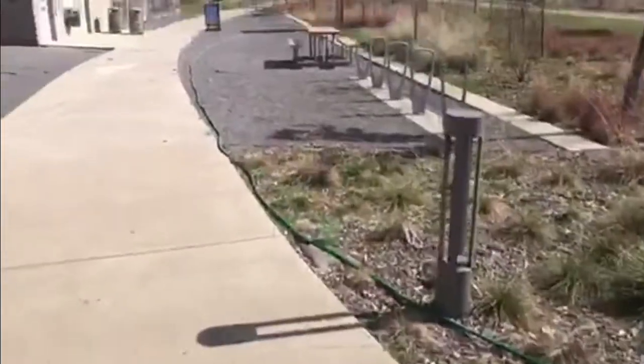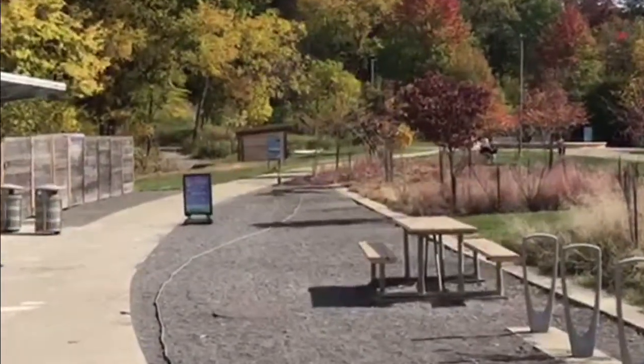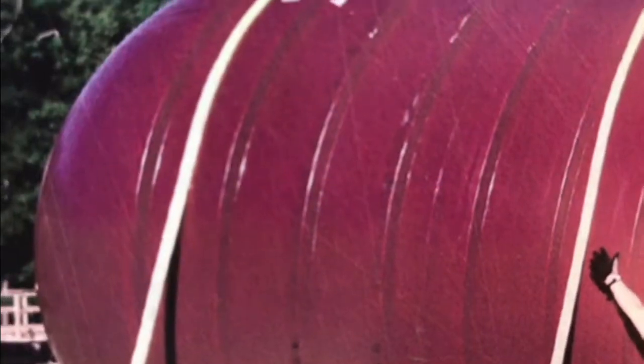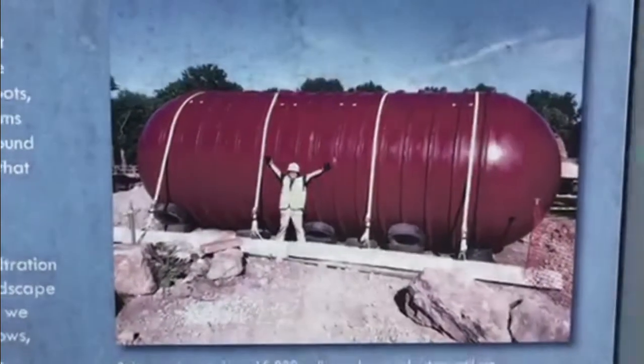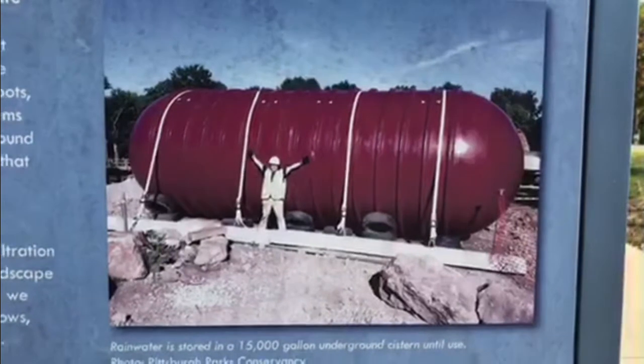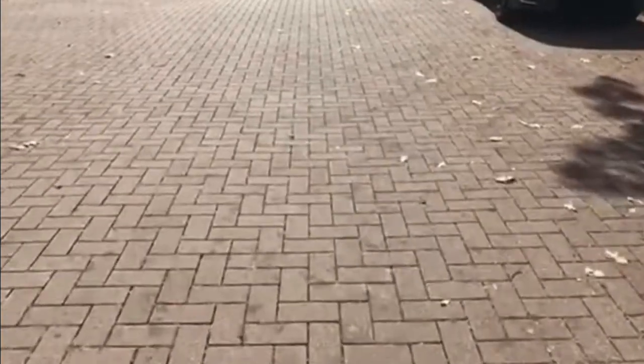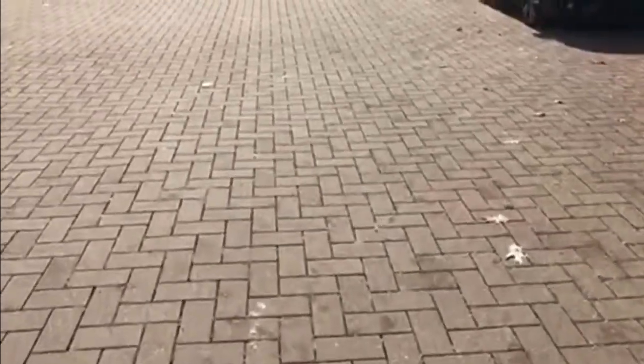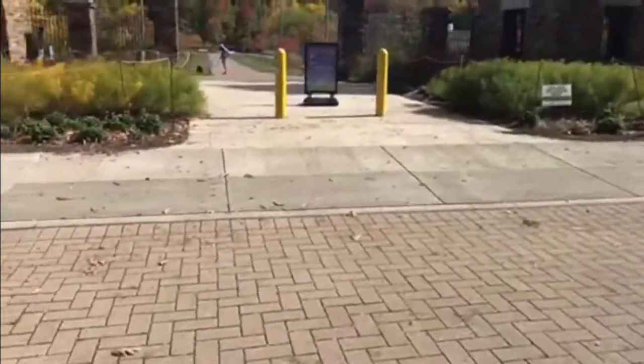Captured water is also stored in a 1,500-gallon cistern near the barn and a 15,000-gallon cistern underground. This captured water is used around the building and landscape. The parking area near the front entrance uses a permeable surface, which allows water to seep underground and be returned at a natural rate. The parking lot under the solar panels is paved with impervious asphalt, so water is captured at underground infiltration areas where the water can be held before being returned.